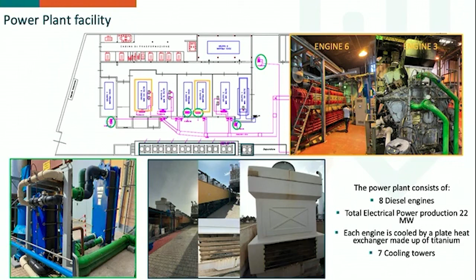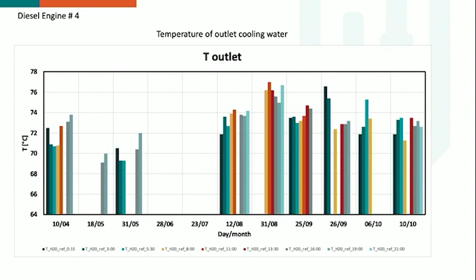In the next 2 slides, you can see we have collected a lot of information regarding the outlet temperature of this cooling circuit, which is what we need as a driving force for the evaporator unit. We have a temperature range around 70 to 76 from diesel engine number 4. The different bars illustrate different hours per day, so it's quite stable, around 72 as an average.